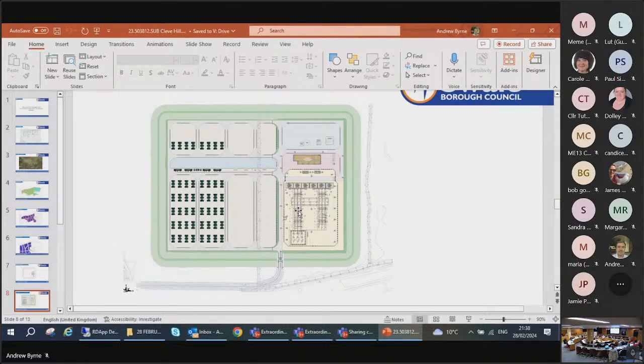The mitigation and hazard prevention capabilities that mitigate that risk are the data analytics, integrated into the battery management and energy management system. These include the controls and monitoring systems, the gas detection equipment, and the gas exhaust system to prevent explosion levels reaching 25% of the lower flammable limit, the lower explosive limit. Details are contained in my reports and the final review to interested parties, which cover this in significant detail.